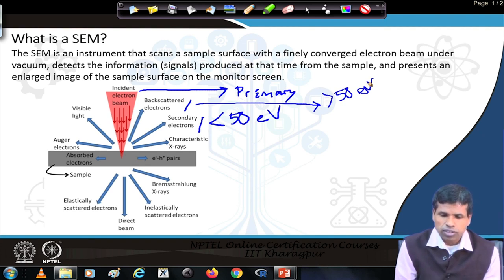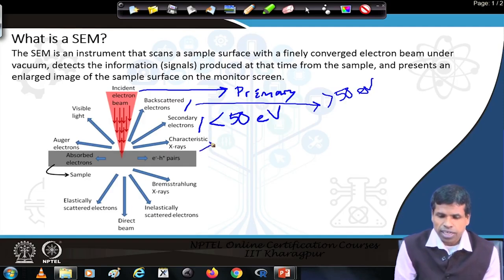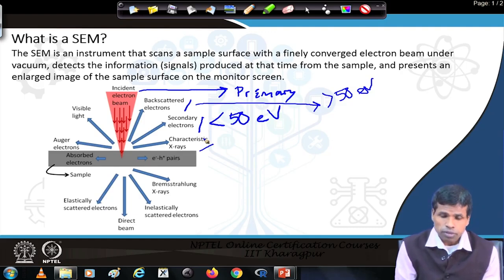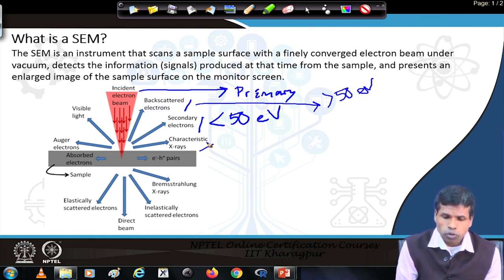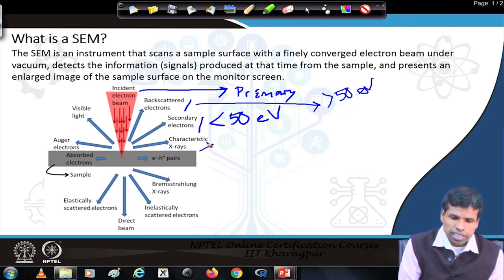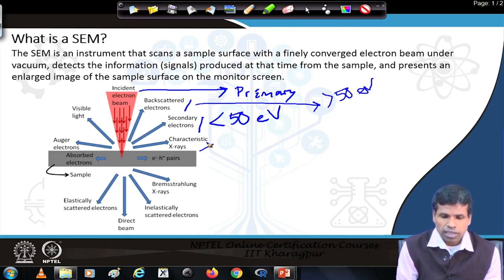In addition to secondary and backscattered electrons, we also get X-rays — these can be characteristic X-rays or continuous X-rays. The characteristic X-rays are utilized for elemental composition analysis: we can know what elements are present in our sample and what percentage of those elements are present. Additionally, light can be generated when the electron beam is incident on the sample — electron-hole pairs may be created, and when those pairs recombine, light may be produced if the sample is semiconducting in nature.